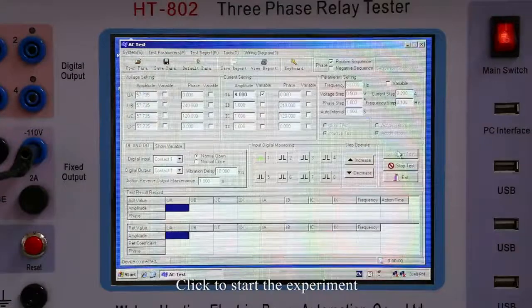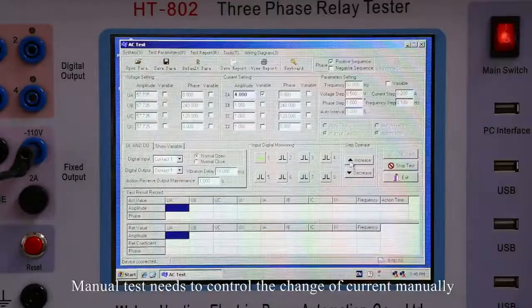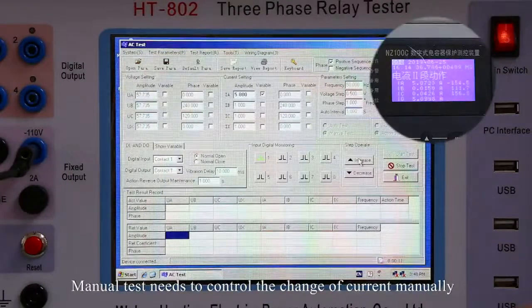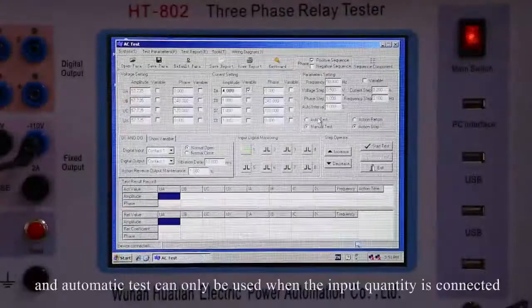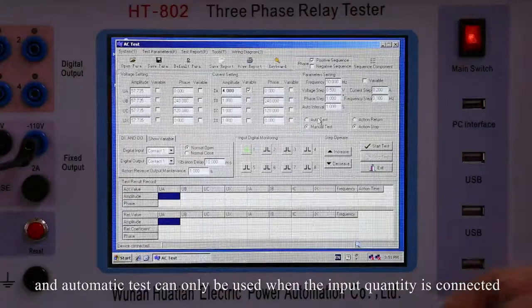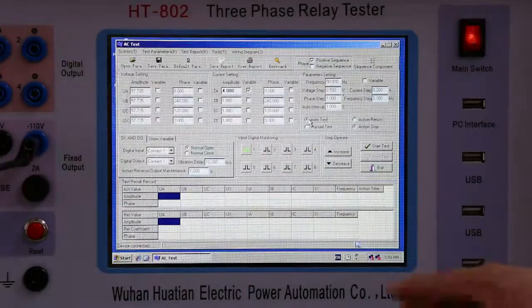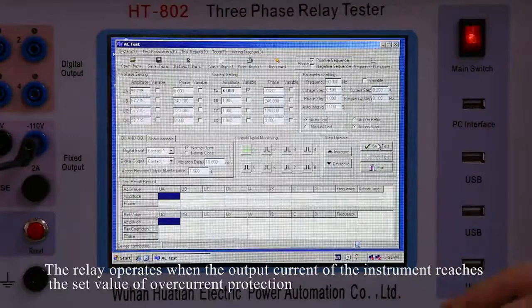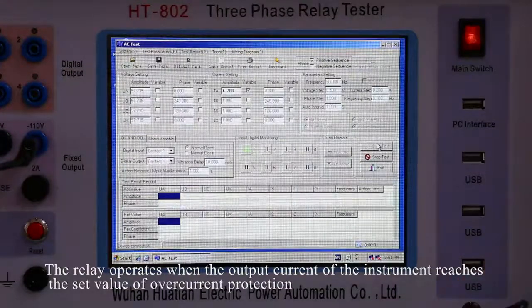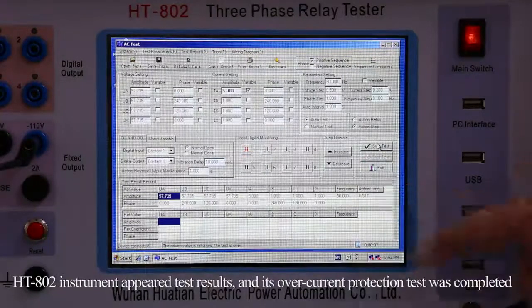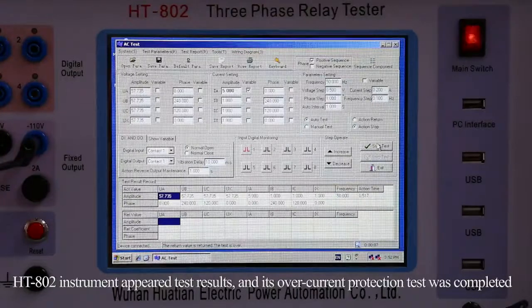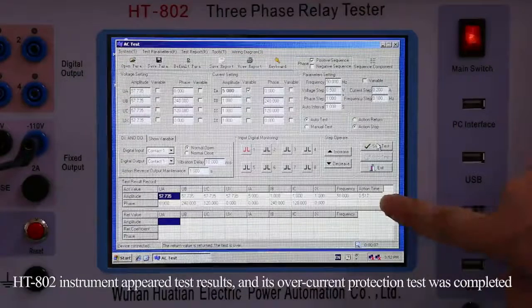Click to start the experiment. Manual test needs to control the change of current manually, and automatic test can only be used when the input quantity is connected. The relay operates when the output current of the instrument reaches the set value of overcurrent protection. The HT802 instrument shows the test results and the overcurrent protection test is completed.